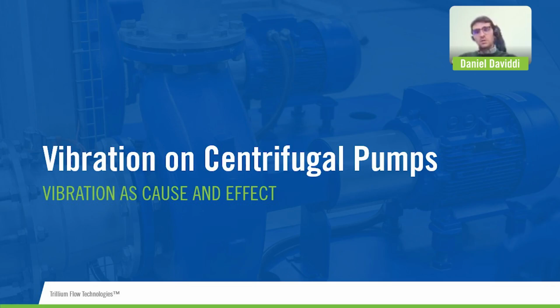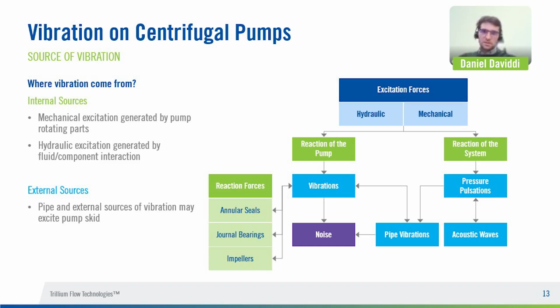Okay, so now let's proceed with the second topic, regarding the vibration that most affects centrifugal pumps. In this slide, we aim to clarify the sources of vibration in a complete centrifugal pump skid. We can basically have two sources of vibration, divided by the location where they come from, internally or externally.